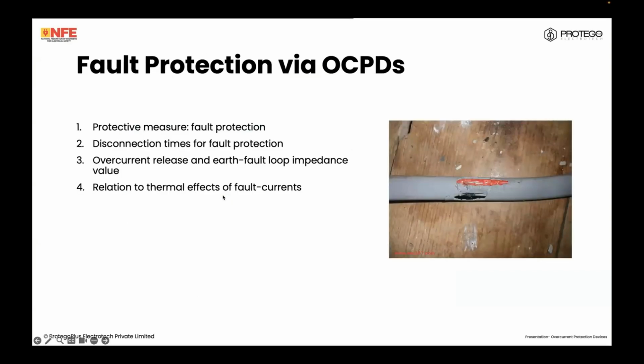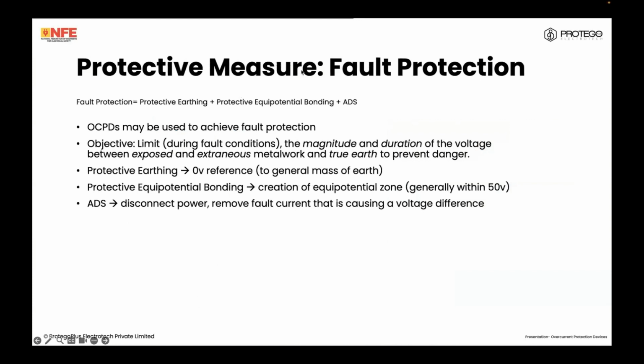Okay, so how do we achieve fault protection via OCPDs? The basic idea is we have fault protection, which is a protective measure. We look at disconnection times under fault protection, how the overcurrent release and earth fault loop impedance relates to this, and the relation to the thermal stresses of the fault current, which is your I squared T value. Remember, again, I'm just recapping here.